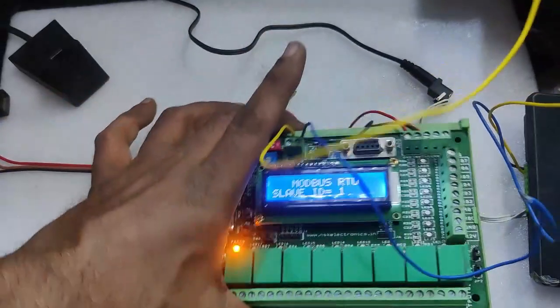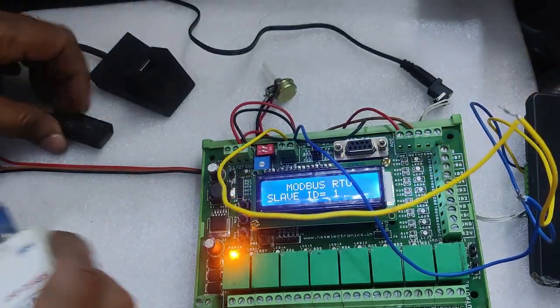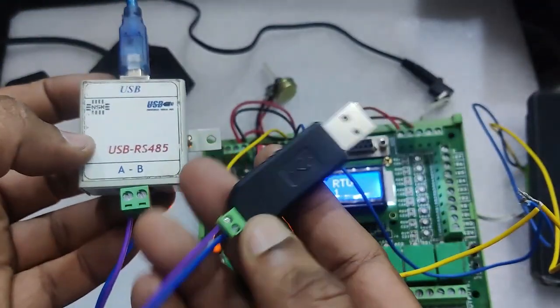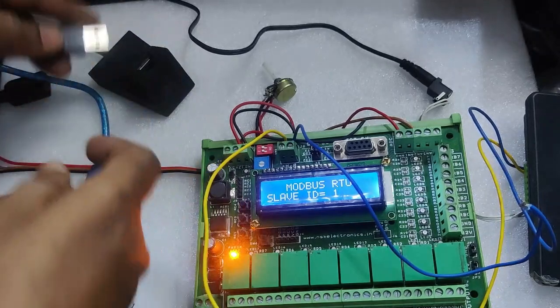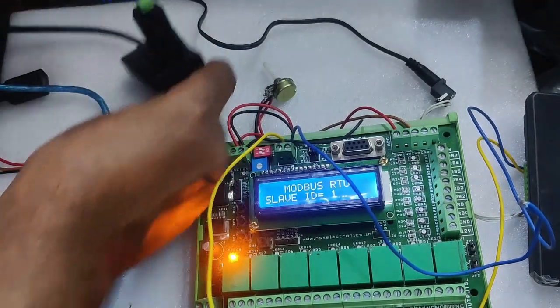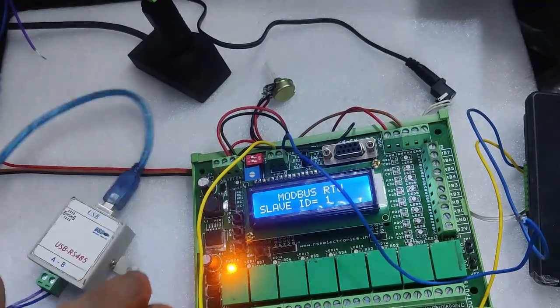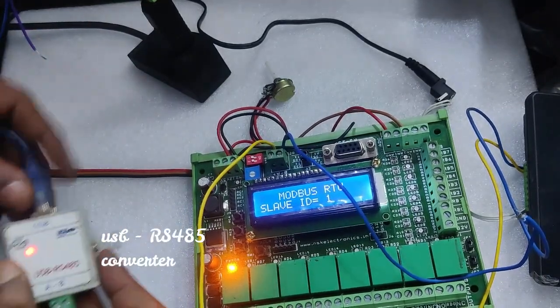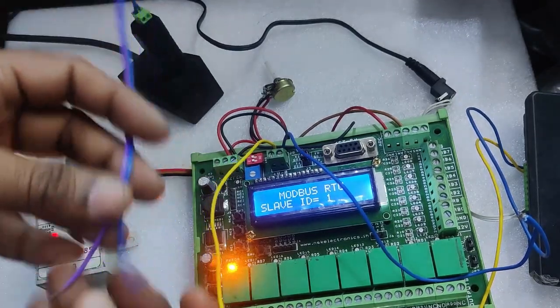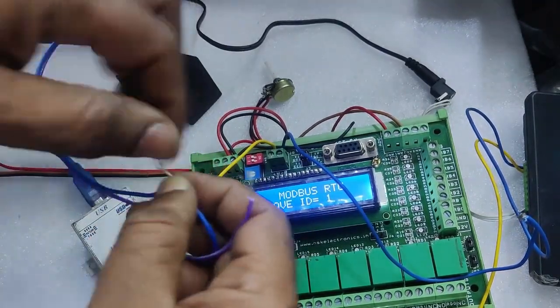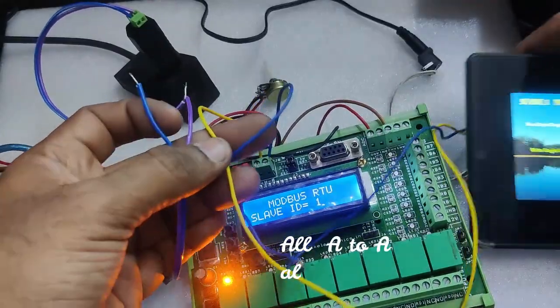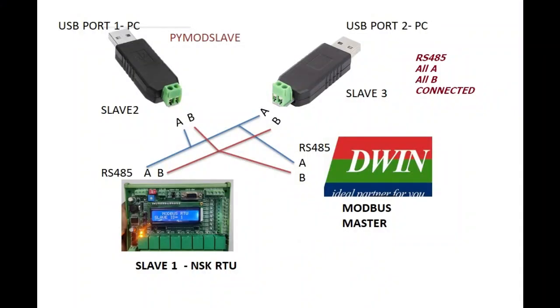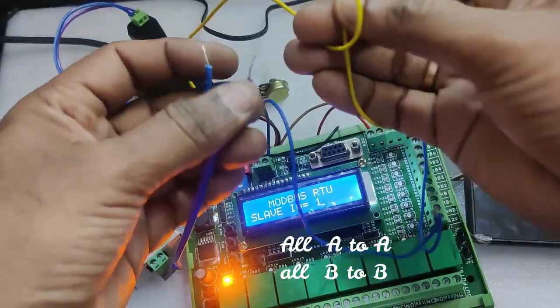The connection between all the slaves is common, that is RS485 has two wires, A and B. So we are using RS485 to USB converters like this, which is connected to one port, and the second RS485 to USB is connected to the second port. All A wires are made common and all B wires are made common to slave 1. Slave 1 is actually the port, and we use this software slave. Now slave 1 is Modbus RTU, and slave 2 is from PC, slave 3 is also from PC. This is the actual connection. All A connections common and all B connections common.